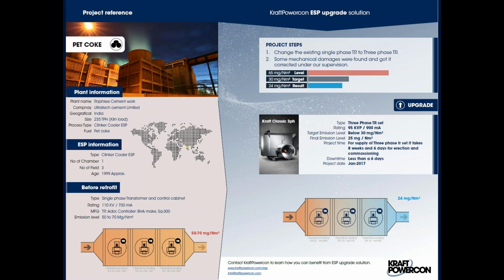This is where we changed a single-phase TR to a 3-phase TR. We also corrected some mechanical damage in the precipitator, and our precipitator knowledge helped here because we had our consultant go in, do the inspection, and write the punch list for the customer to correct. So this is where we're more of a solutions provider—the customer came to us with a problem and asked how we could fix it. We said we needed to do some key repairs to their precipitator and go from single-phase to 3-phase. Again we had a good result: 65 milligrams per normal cubic meter, which was above their limit, and we drove it down below their target so they'd have operating margin over time.